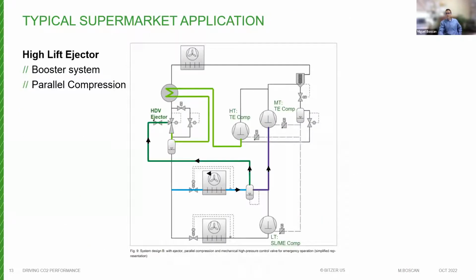In a booster system with ejectors, a portion of the medium temp evaporator mass flow is diverted through the ejector back to the flash gas tank after the medium temp evaporator. That's the dark green line right here, off of the suction accumulator back to the ejector. The remaining mass flow combines with the low temp mass flow and returns to the medium temp compressors, which is seen here in the purple line. The pressure of the flash gas vessel is maintained by the parallel compressor, shown in the light green line right here.